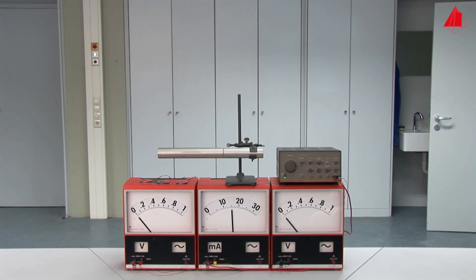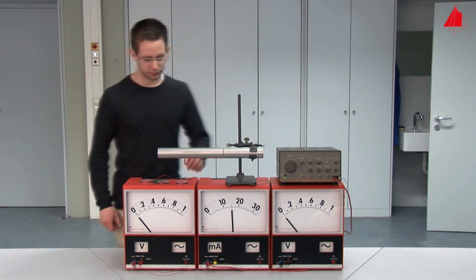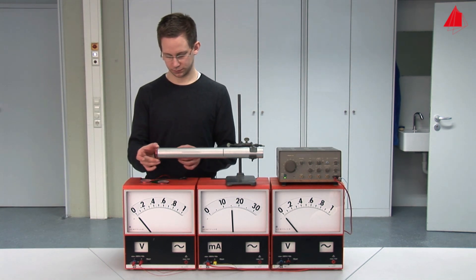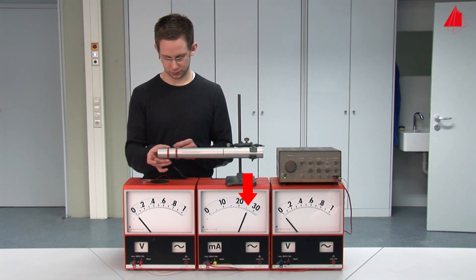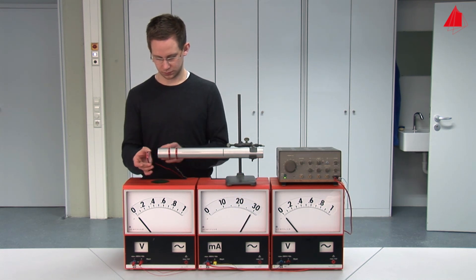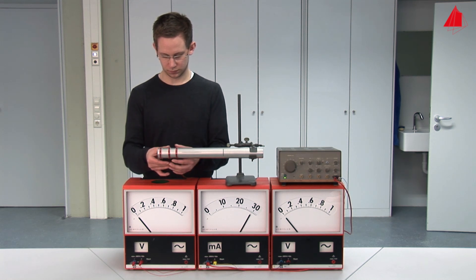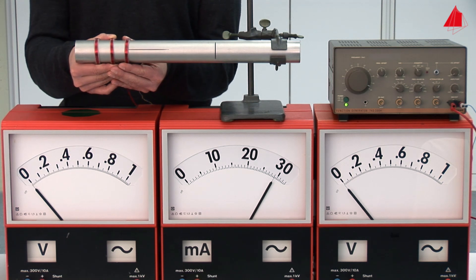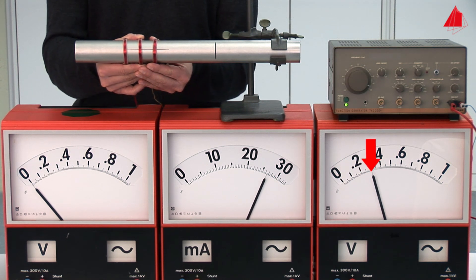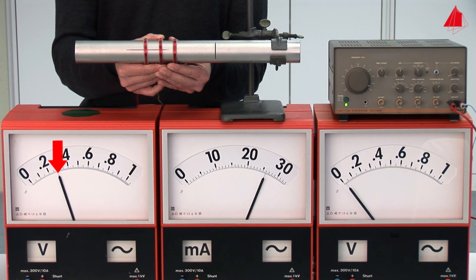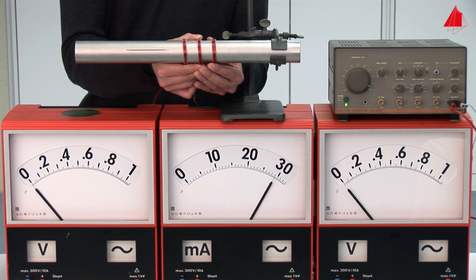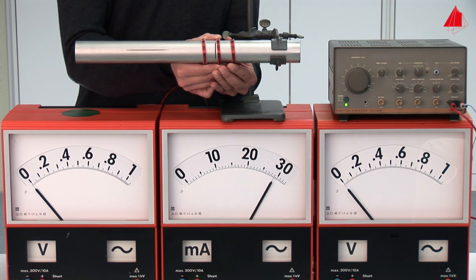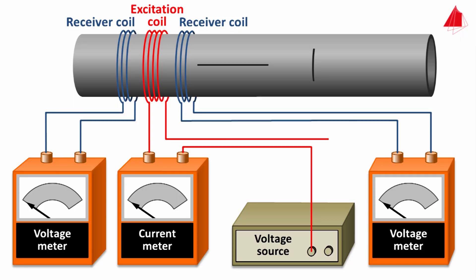The improved test arrangement has been set up in the laboratory and is now in operation, as can be seen from the current consumption of the excitation coil. The materials tester first places the right receiver coil over the tube, then the excitation coil — causing the current consumption to increase as in the previous test — and finally the left receiver coil. He then carefully moves all three coils to the right. The pointer of the right voltage meter deflects, then the pointer of the left voltage meter. In the intact region of the tube, neither voltage meter deflects. Unfortunately, the saw cut in circumferential direction is again not detectable.